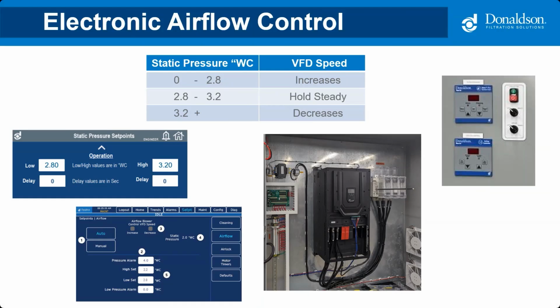The VFD controls the speed of the motor, which reduces that inrush current even better than a soft starter. This increases the energy savings from the utility's peak billing. And also when the operating conditions will allow for the motor speed to be reduced to about half, or 3/4, or just any amount of hertz that's less than full speed, energy savings will be increased compared to a standard motor starter or a soft starter, which operate only at full speed. Next, we'll talk about adding some additional motors and components.